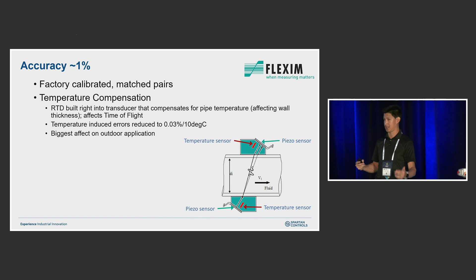So how do we get that 1% with a clamp-on ultrasonic meter? We do factory calibrated pairs, so those two transducers are matched together. But the key differentiator is that there's a temperature sensor built into the piezoelectric crystal, which gives us direct temperature compensation. A lot of clamp-on ultrasonics on the market use a temperature sensor outside of the transducer, which may not be representative of the temperature the transducer is actually seeing, and those are the temperature effects we want to compensate for.